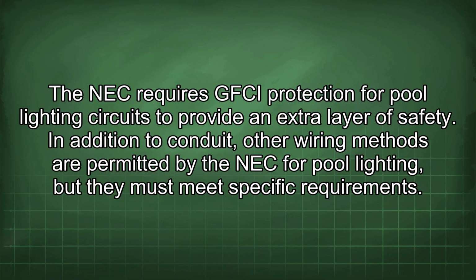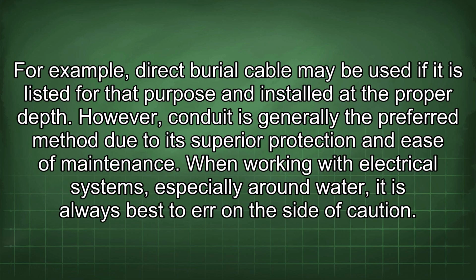In addition to conduit, other wiring methods are permitted by the NEC for pool lighting, but they must meet specific requirements. For example, direct burial cable may be used if it is listed for that purpose and installed at the proper depth. However, conduit is generally the preferred method due to its superior protection and ease of maintenance.